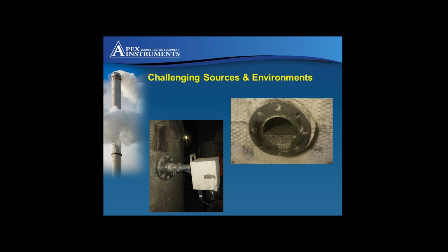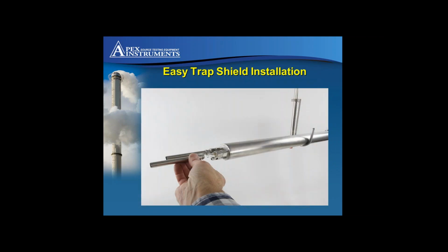Seen here, you'll see that some sources can offer a challenging environment for continuously extracting a sample. High particulate, wet FGDs, and lime injection are some of the challenges for 7-day sampling. Choose the right trap configuration to suit the sampling environment. Particulate, acid gas and moisture can cause sampling issues. This is where trap configuration can help with process conditions. Additionally, trap shields can protect each trap. An illustration of the individual trap shields, ensuring no restriction for the pre- and post-leak checks.